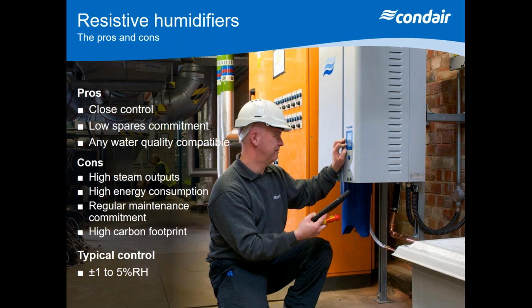The steam outputs are going to be very similar to the electrode boiler, anything from 5 kilos up to 90 kilograms an hour. You're still going to be boiling the same amount of energy, obviously, to give you steam, but this is going to be a way of giving you some good close control with lower maintenance. Now, also the consumables with these are going to be less. You can imagine with the electrode boiler, you could be spending £300 or £400 a time to replace those. Now, the consumables on these are normally going to be like gaskets, seals, or this particular one you can see in the picture, a scale collector, every so often. So there is less to consume in terms of spare parts, but what you've got to consider is these are a bit more expensive than your electrode boiler, probably about 3 times the cost, but it's horses for courses with this. If you've got close control and you want to have less downtime, a resistive humidifier is the way to go.